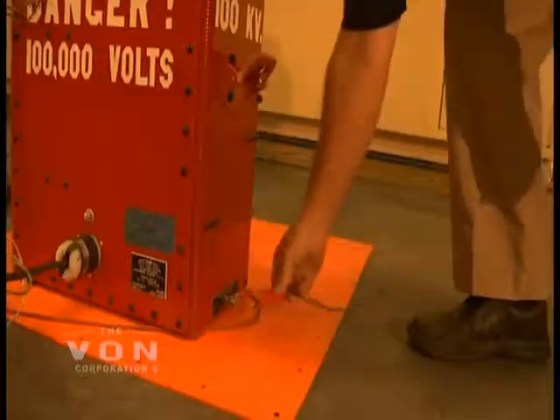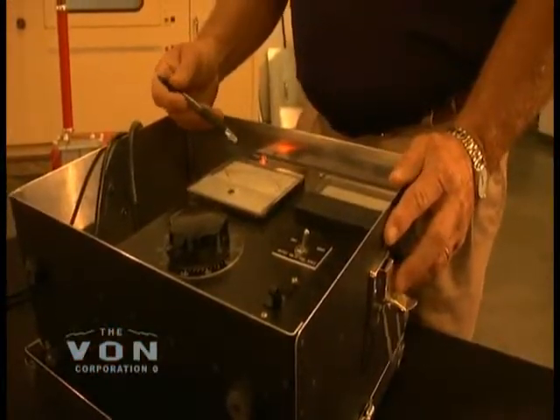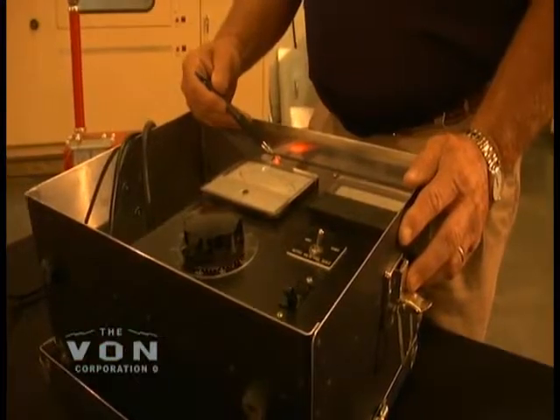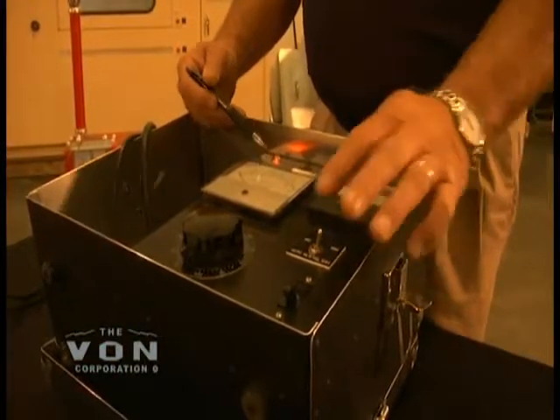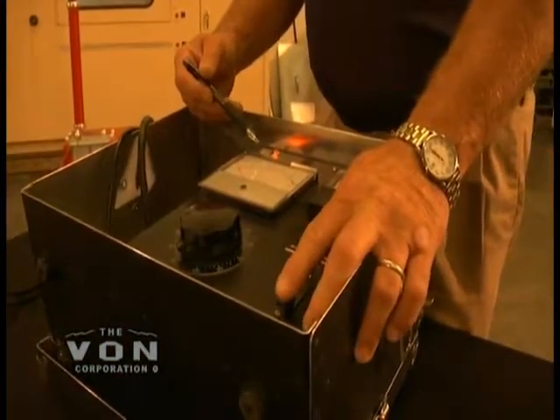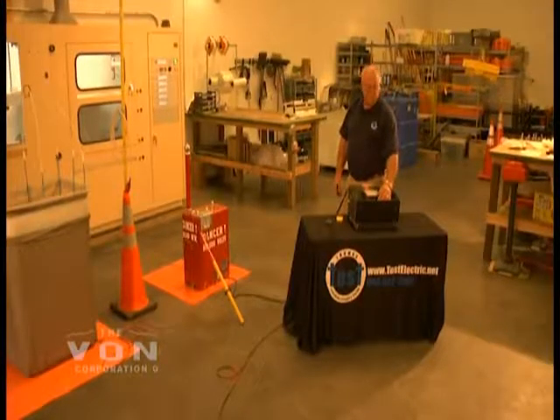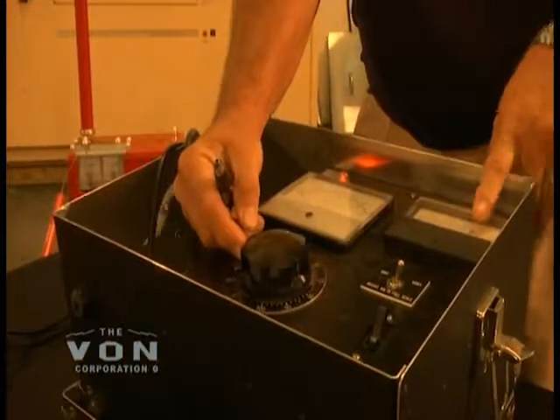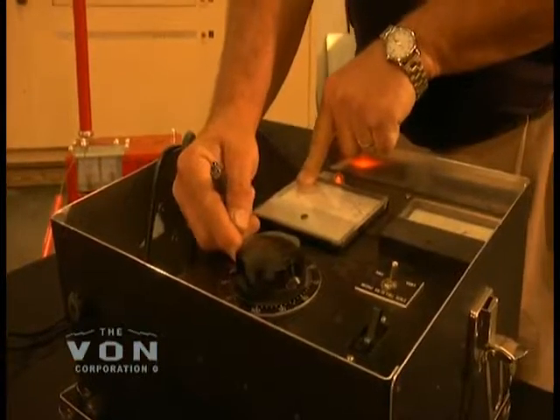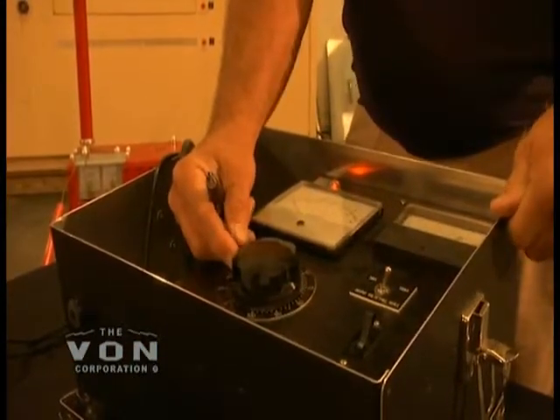It's always best, the first time you use the unit each day, when the ground relay is on, to turn the unit on, leave it grounded, and raise the voltage slowly. Your amperage should increase while your voltage stays at 0. This ensures that the unit is connected properly and grounded properly.